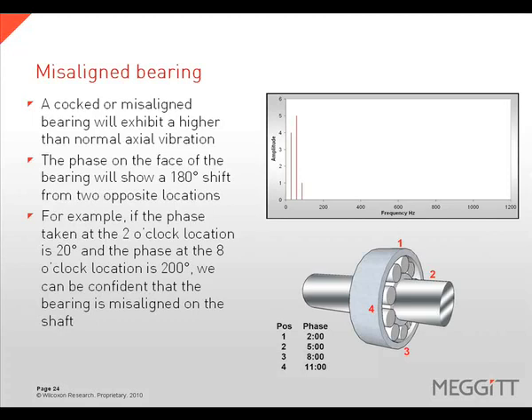A bearing that is cocked on the shaft will exhibit higher than normal levels of vibration in the axial direction at 1x and more significantly at 2x rotational speed. The best method to distinguish a cocked bearing is to take axial phase readings around the face of the bearing. If the bearing is straight on the shaft, the phase will remain steady within plus or minus 30 degrees. In the case of a cocked bearing, there will be a 180 degree phase shift from one position to the opposite position — for example, 20 degrees at the 2 o'clock position and 200 degrees at the 8 o'clock position.